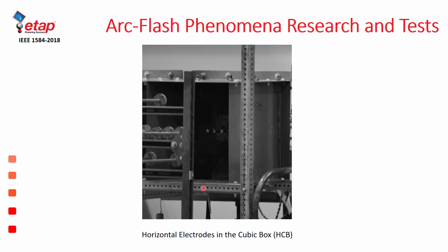This configuration may be less common, but if present in actual equipment, it may yield the highest energy flux per second and an arc current with lower magnitude than that of the vertical conductors in a box configuration. The lower current could significantly compound the issue because lower currents can yield longer operating times in overcurrent protective devices and therefore create a larger calculated incident energy value, especially when you compare to the existing VCB configuration from the 2002 model.